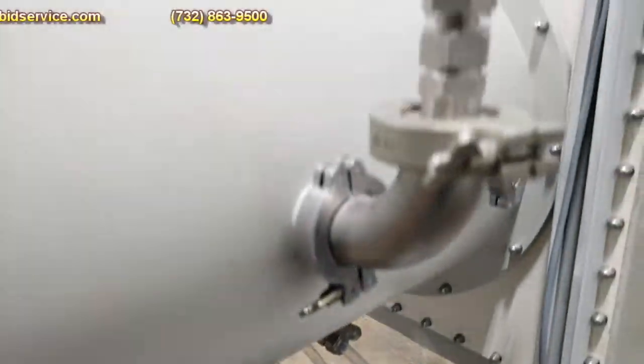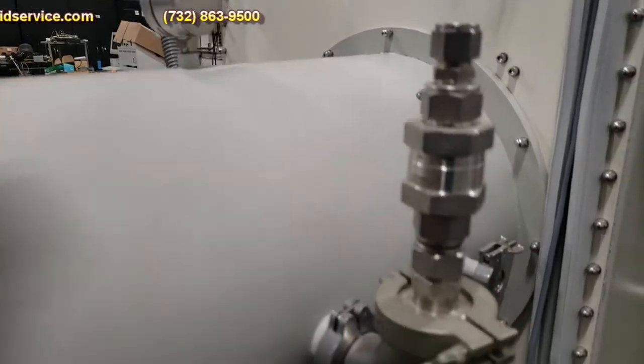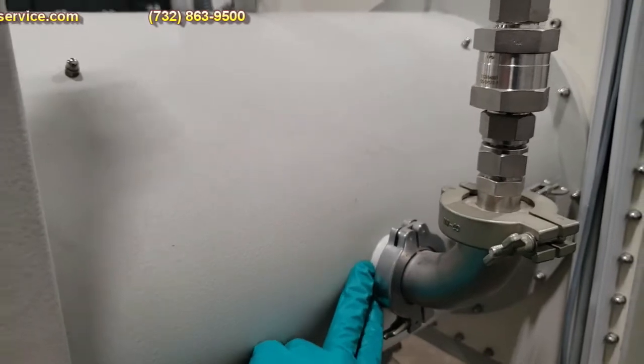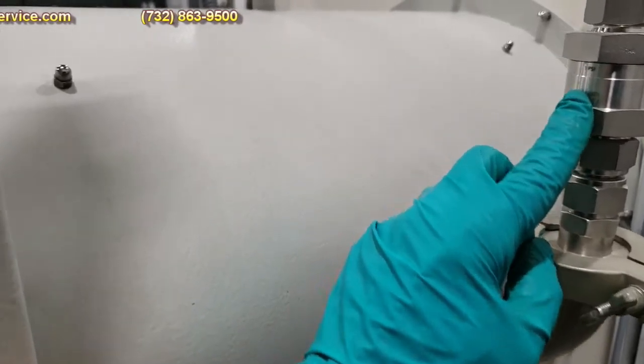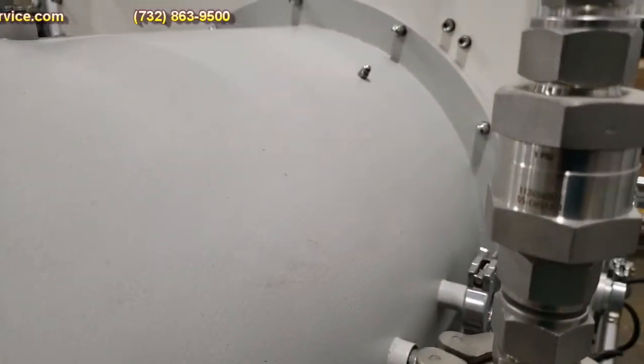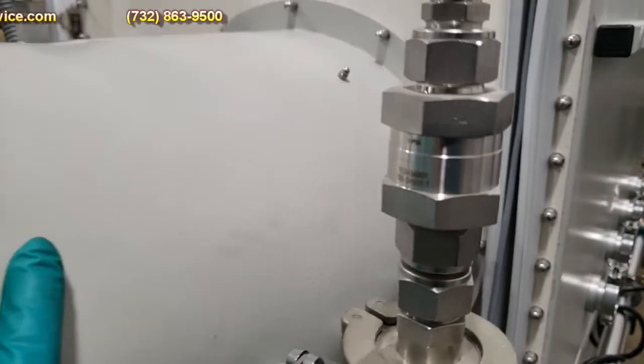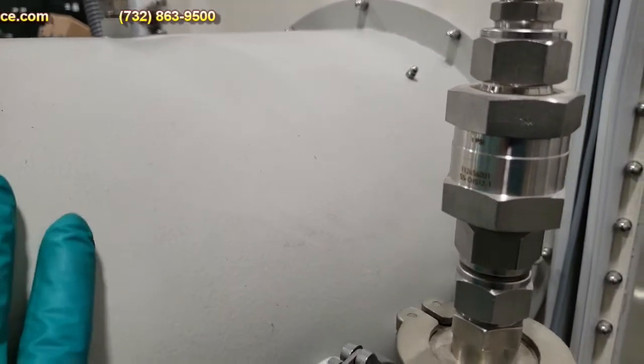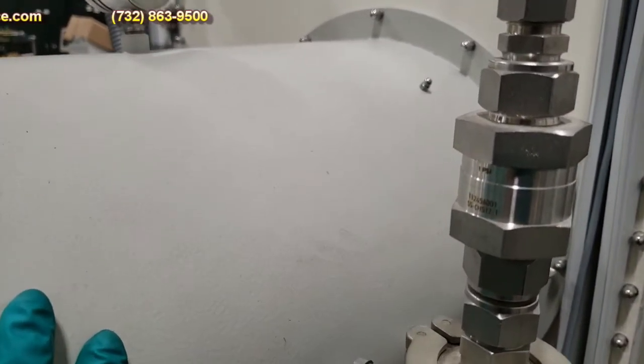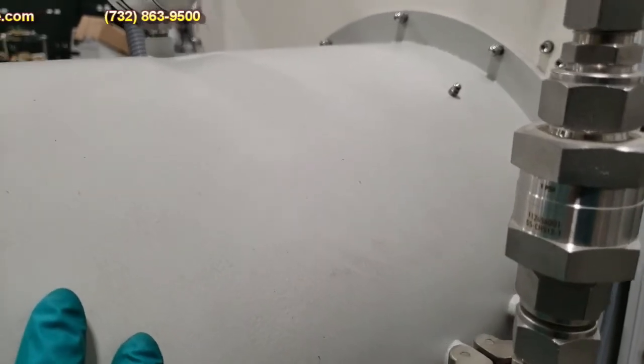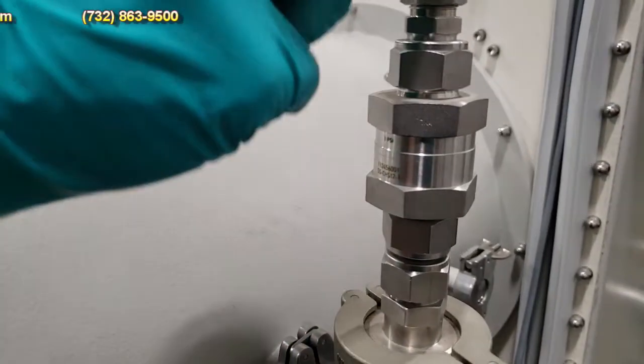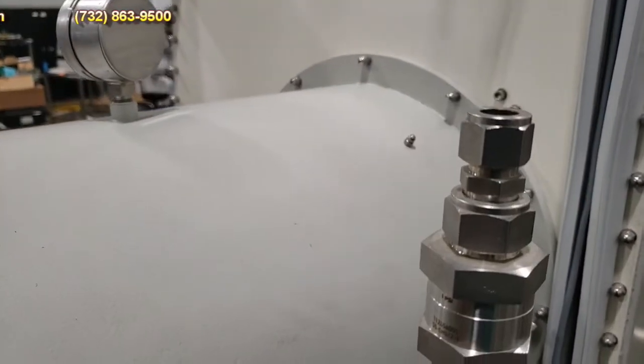I want to point out too, because you're using a cylinder, they put a check valve on the large antechamber, set at 1 psi. That way you won't overpressurize your antechamber if you forget to shut it off once it reaches atmospheric pressure. You don't want to pressurize it up to the cylinder's 90 psi. So they put a check valve here, and it's just exhausted out this opening here.